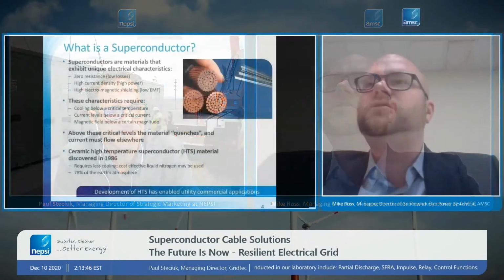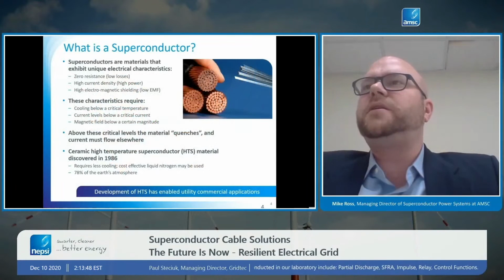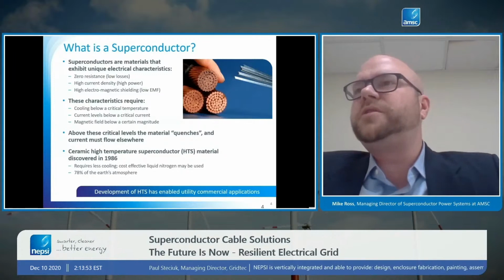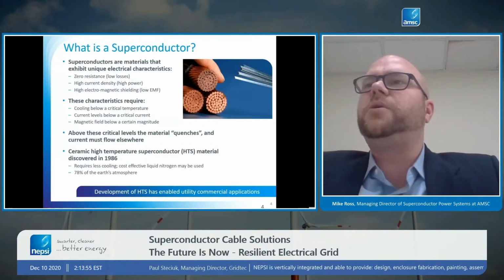It's amazing. And that's really what drives the benefits and the value of this technology to utilities, that current density. In order to achieve that superconducting state that allows us to get that current density, though, there are some things that are needed, and the key one is that we have to cool the material. So we need to cool the material down to about minus 200 degrees Celsius. So very cold. That's the area where nitrogen is liquid. So we use liquid nitrogen to cool the cables.